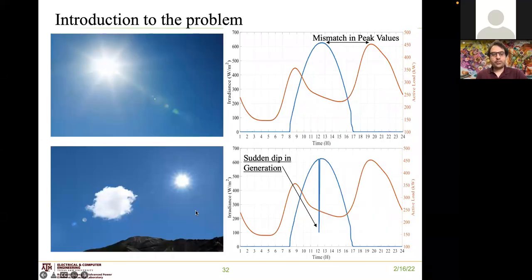So now let's try to look at this problem more intuitively. Take a look at the picture on the left-hand side. We have a very bright sunny day. If we have a solar panel that's connected to our network, and if you take a look at the irradiance, or the amount of sunlight that's falling on the panel, we'll see that the irradiance follows a very smooth curve since we're having a bright sunny day with no clouds. But imagine a scenario where a cloud just swoops in and blocks the sunlight that's falling on the solar panel. At that point, there will be a dip in the irradiance profile and hence a dip in the generation as well. And it's important to remember that these solar PV curves keep on changing throughout the year, depending upon the sun's position in the sky.